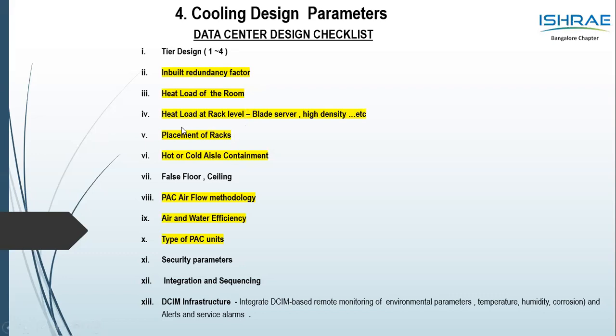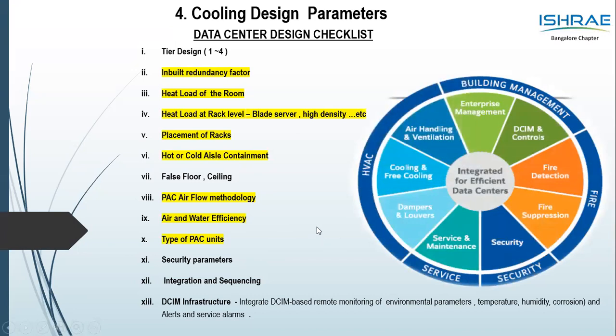So placement of rack is very important. Cold and hot aisle containment, I have a slide and video on this in the next slide. Airflow methodology, we will look at the different types of airflow methodology within a cooling system. Improving the air and water efficiency. Very important to look at the right temperature and right chilled water temperature to be maintained within a data center. And we will also look at the different types of precision AC unit. Integrating all of this through a DCIM, data center infrastructure management, so that it becomes like a brain of the equipment to monitor, control and sequence all of these critical parameters.